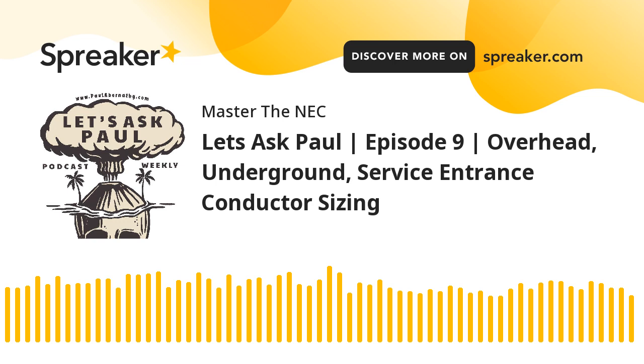Okay. Now it goes on to B. It says, okay, overhead service conductors, a minimum size. It says the conductors shall not be smaller than 8 AWG copper or 6 AWG aluminum or copper-clad aluminum. Remembering that copper-clad aluminum is really aluminum with a copper veneer, if you will. It's metallurgically bonded copper to aluminum.